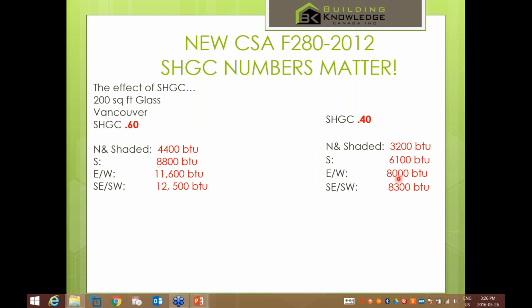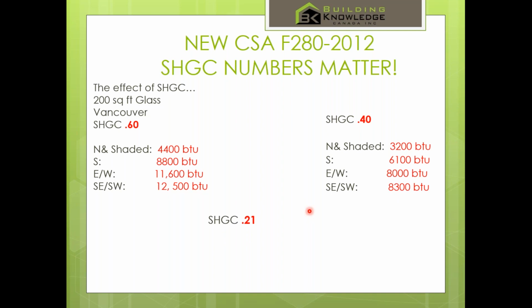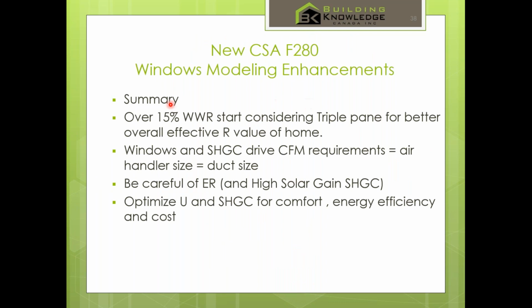If you want to go with a low solar glass in the house and go with something around 0.21, all of a sudden you're down to a third of what you originally were with a high solar gain glass. And if you think this through as you move through the calculations, it's why it's number one, it has such a big impact on the wall. So keep in mind when you're designing homes that when you're doing heat loss, heat gain, that if you have a 15% window to wall ratio, having triple pane windows is actually going to reduce your loads better than putting in, say, 2 inches in some case, or 1 inch of continuous insulation, R5 or R10.